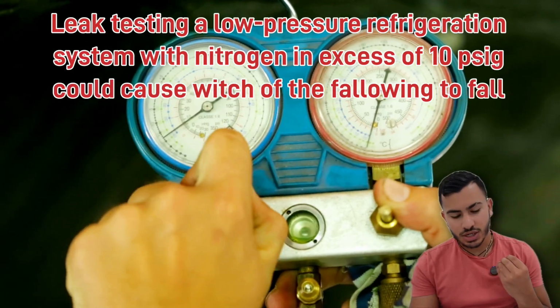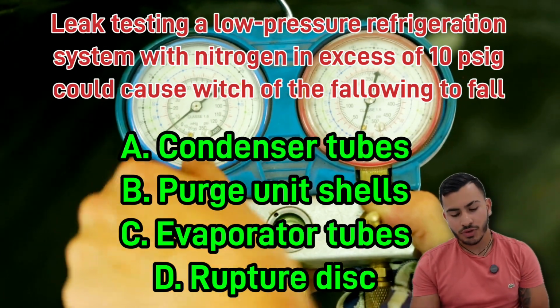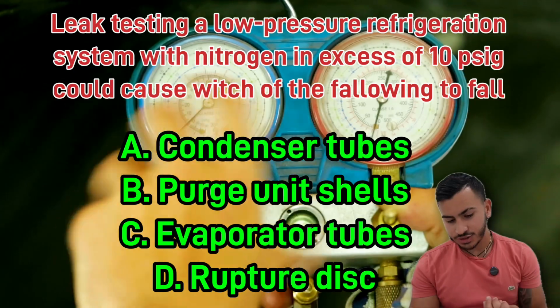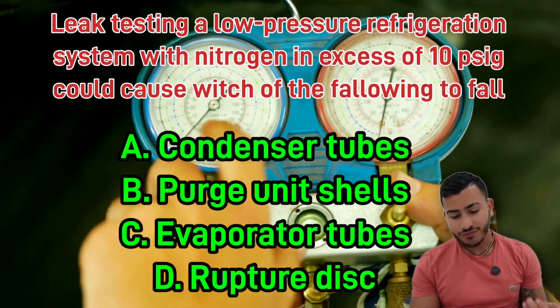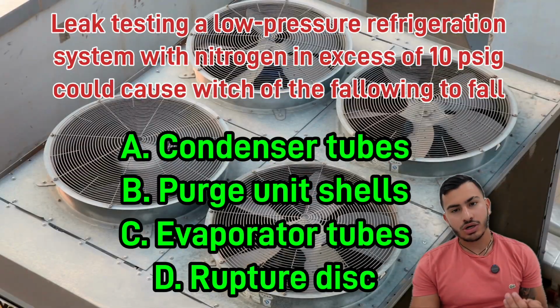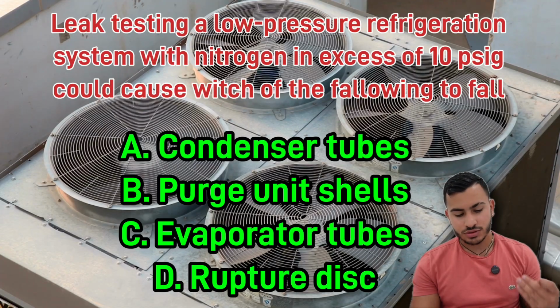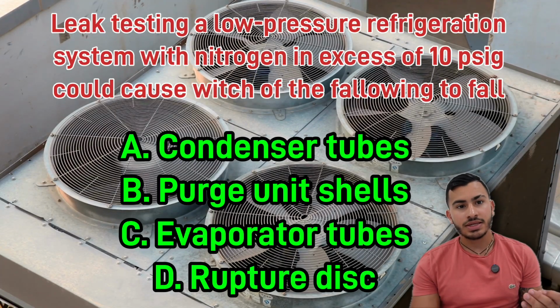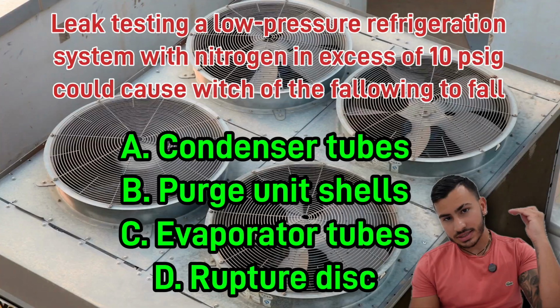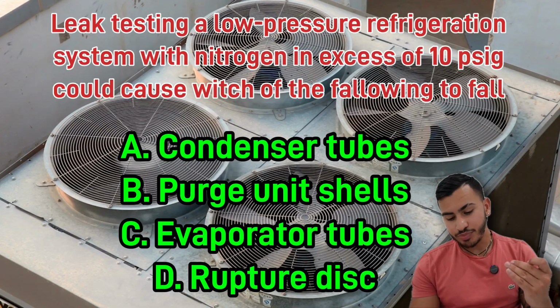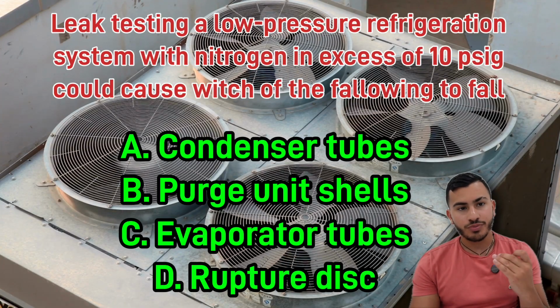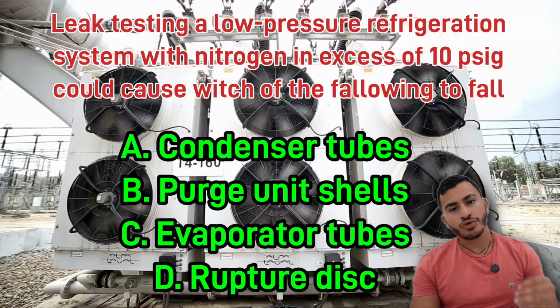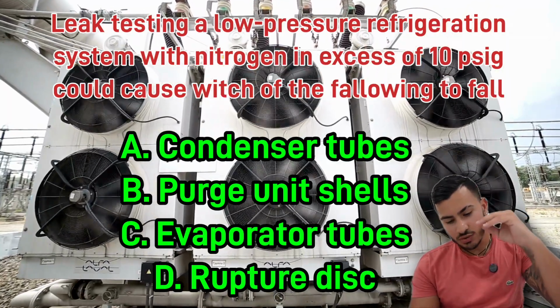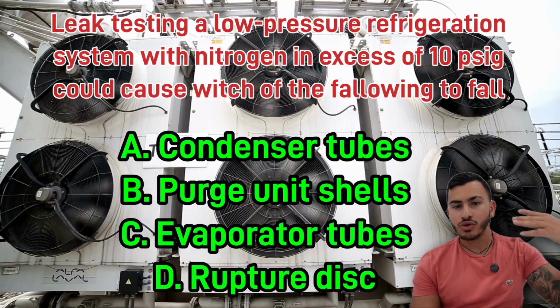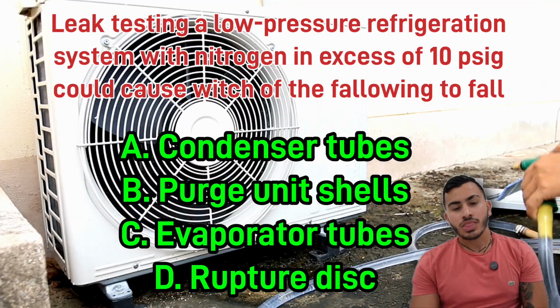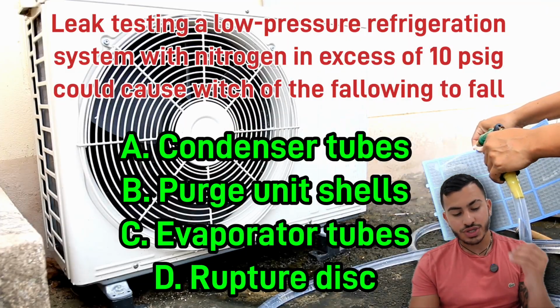Leak testing a low pressure refrigeration system with nitrogen in excess of 10 psi could cause which of the following to fail? Once it exceeds 10 psig, it will be the rupture disc. It will always be the rupture disc, especially when you're talking about type 3 low pressure systems. So for number 2, it will be D.